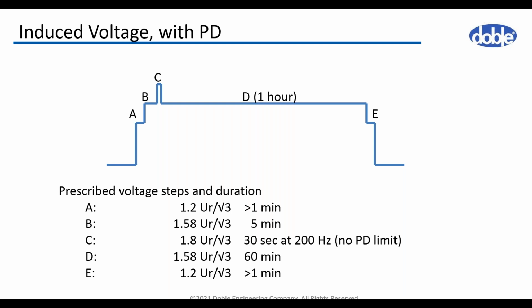If the transformer passed the enhancement level successfully, the voltage is reduced to 1.58 rated voltage for 1 hour, where we measure the partial discharges every 5 minutes. The limit here is 250 picocoulombs. And if that's successful, then we reduce the voltage to 1.2 rated voltage to obtain the partial discharge level again, followed by a repeat measurement of the background level. Good laboratories would have a background noise level of less than 15-20 picocoulombs.